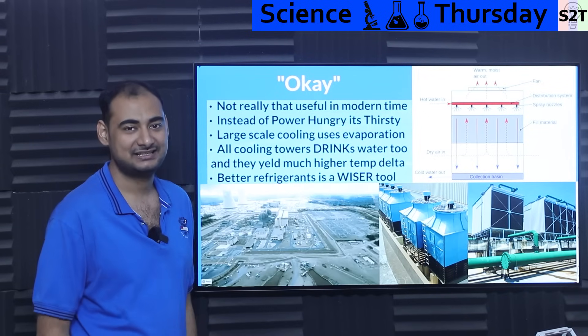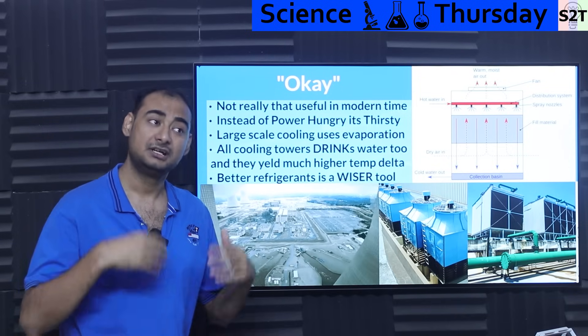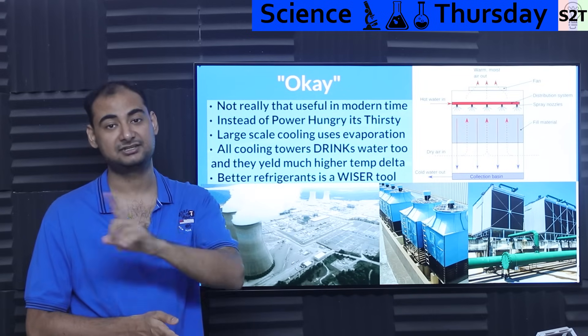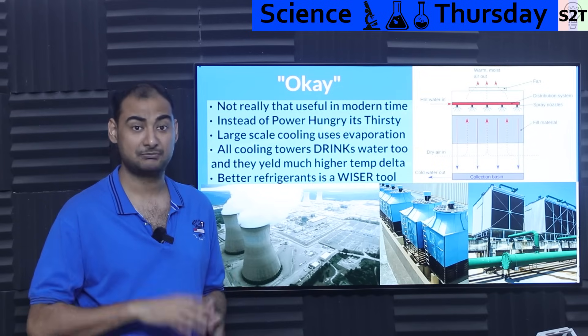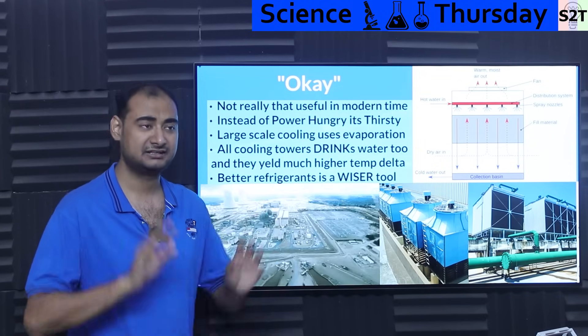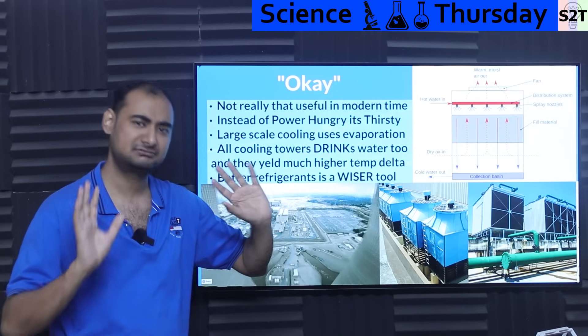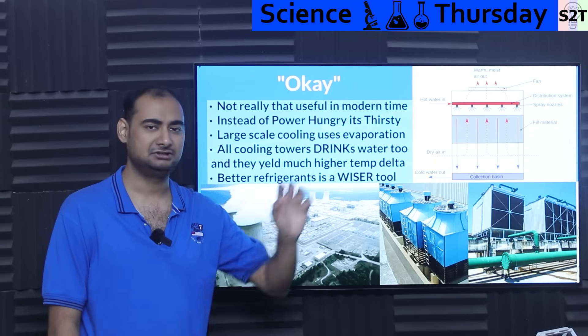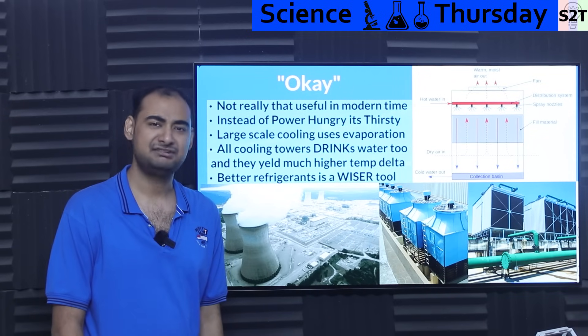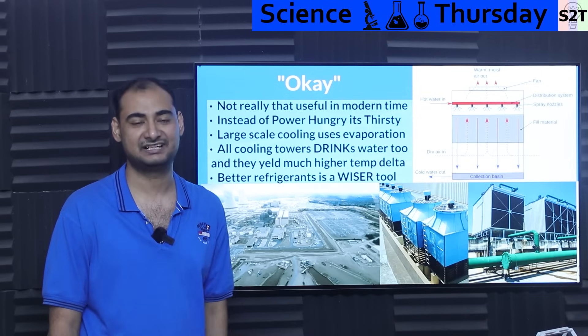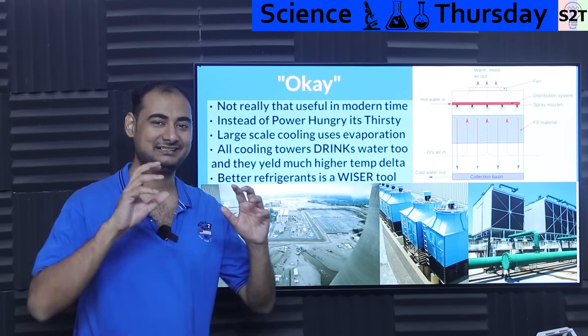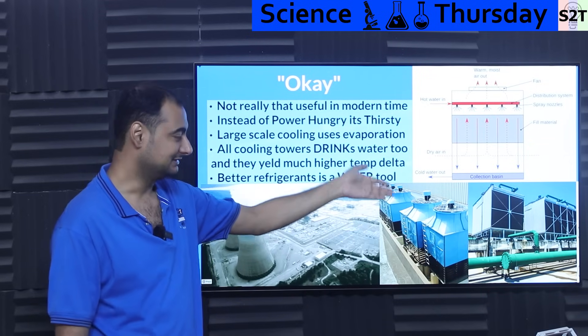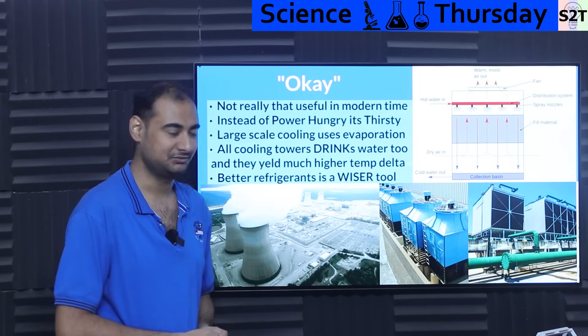Large-scale cooling actually uses the same technology. In India the ISEER rating for the best split air conditioner tops out at about 5 COP, and it never really reaches that. But go into a large building and look at their chiller — they'll have ludicrously high COP, like 9. How? They're cheating: the hot side of the chiller is a swamp cooler. The hot side dumps all the hot water into this system, which evaporates it away. That's what's happening.